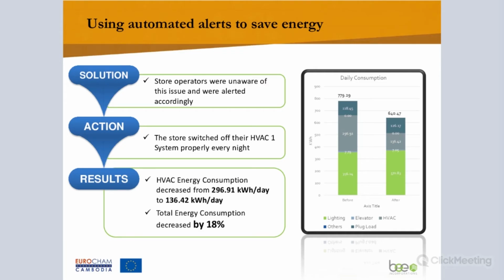This is a chart where we implemented such a measure, from a big retailer in Hong Kong, a store operator, where the issue was that HVAC systems were not properly switched off during the night. This is very typical—I've heard the same from international schools and other building operators. It sounds simple, just pressing a button, but switching off systems that aren't in use is often challenging. We implemented an alert system so they'd be notified if the HVAC wasn't switched off, and by doing so they reduced their energy consumption by 18%.